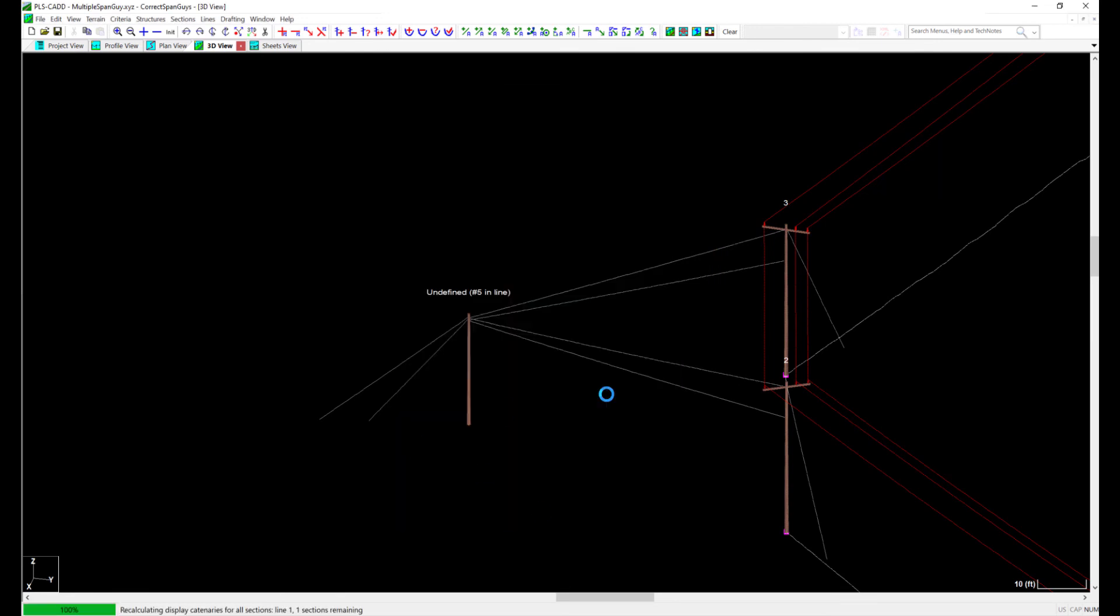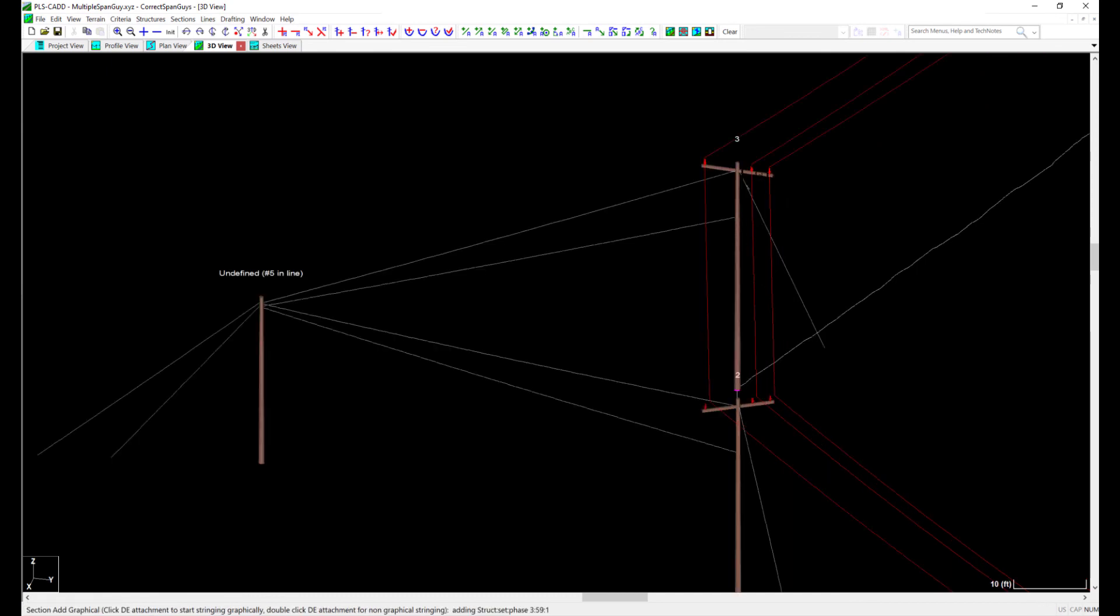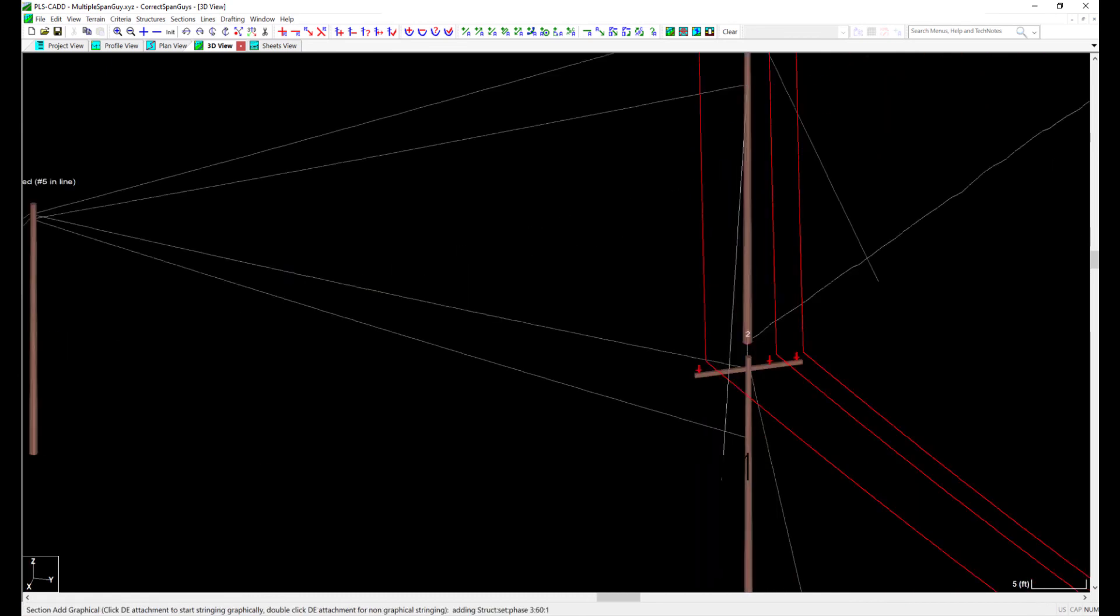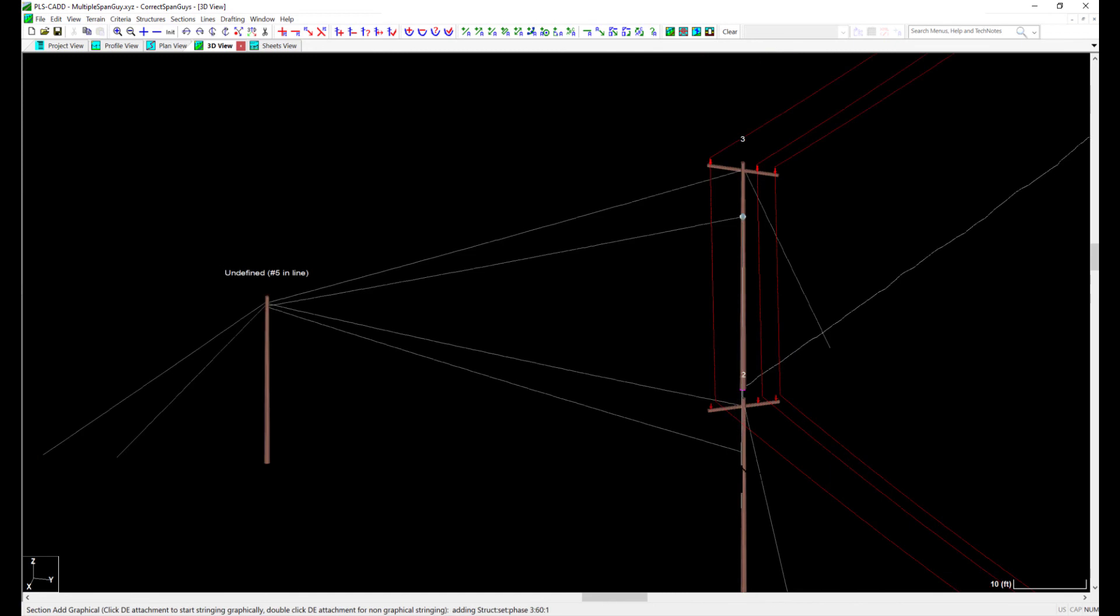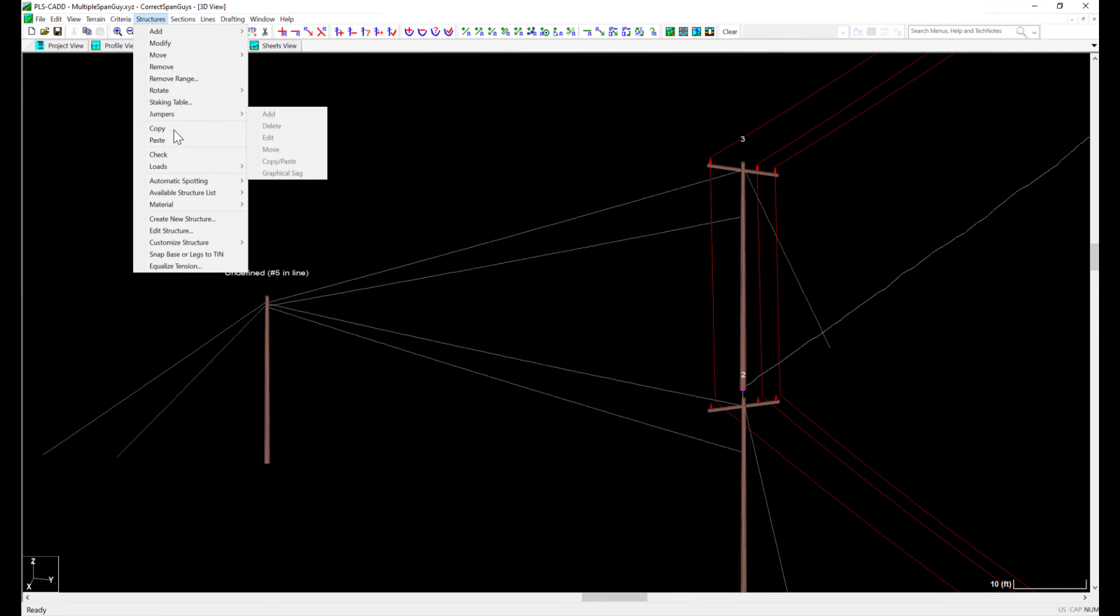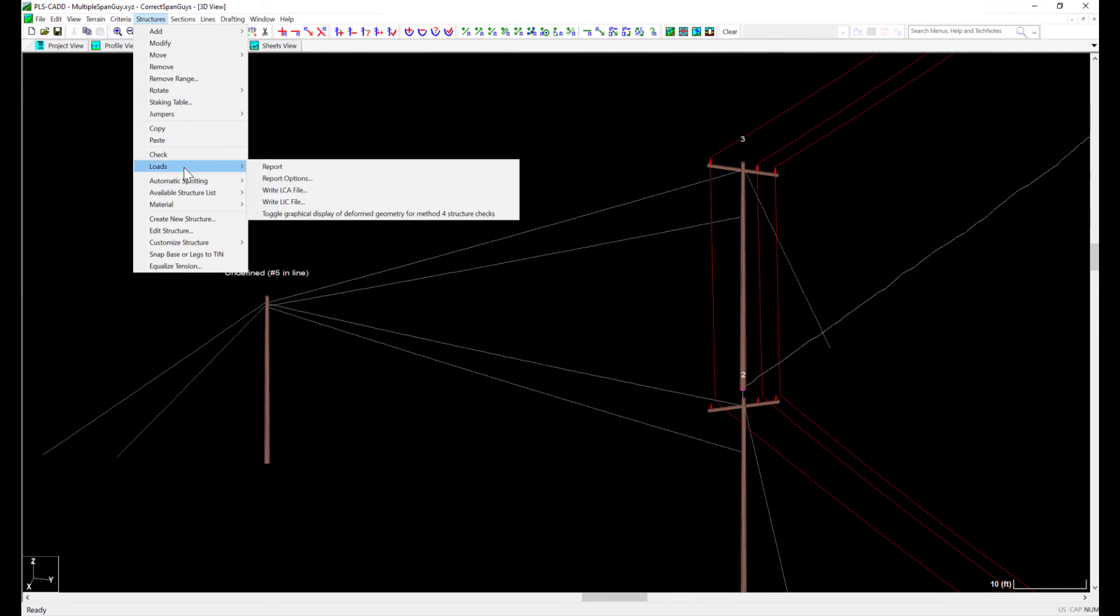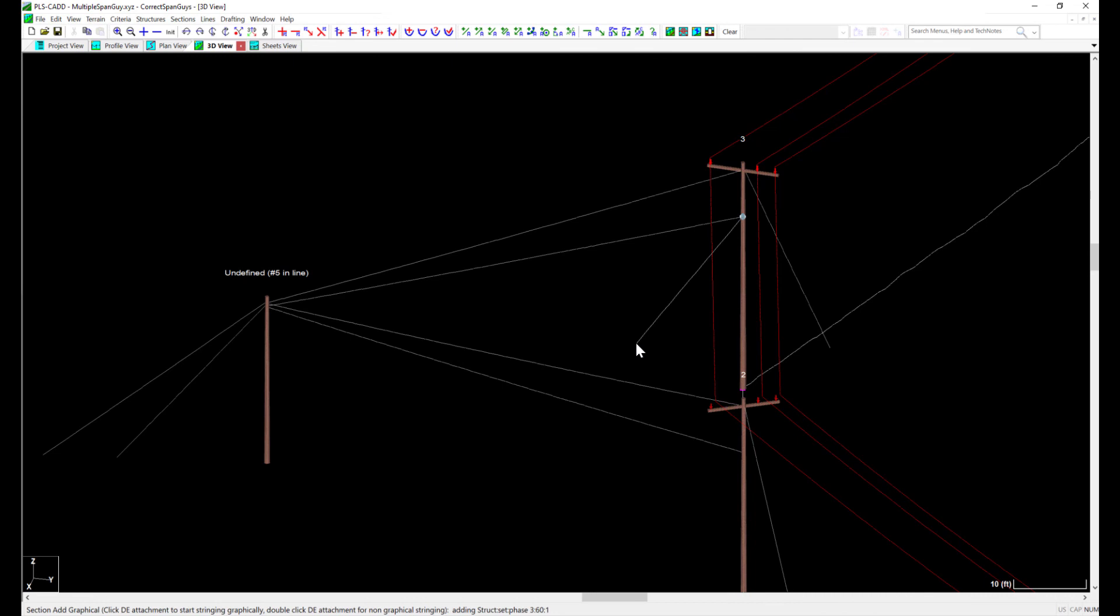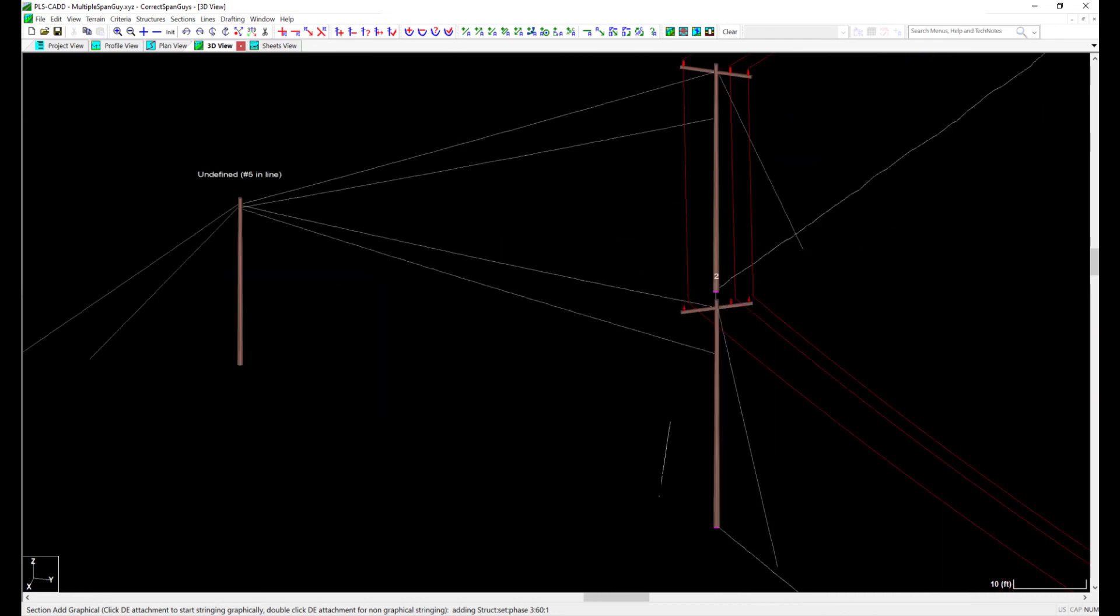Now when I go to my 3D view of the structure, I see that the wires are not connected to the insulators. This is because the pole is deflecting under this load. To show this after the analysis is run, I'll go to Structures, Loads, Toggle Graphical Display of Deformed Geometry for Method 4 structure checks. Now the attachment points will line up with the wire position after I run an analysis.